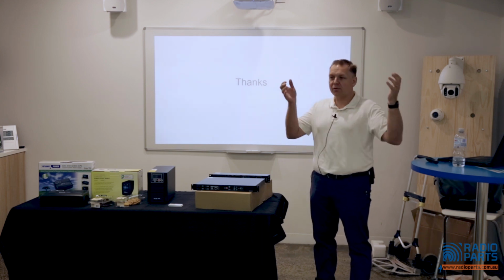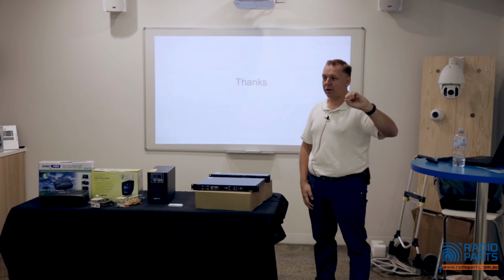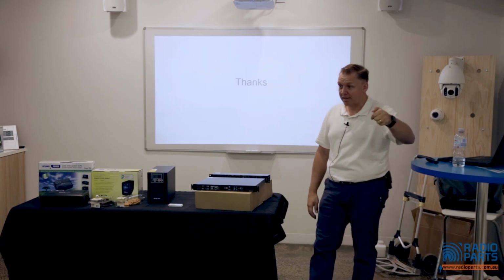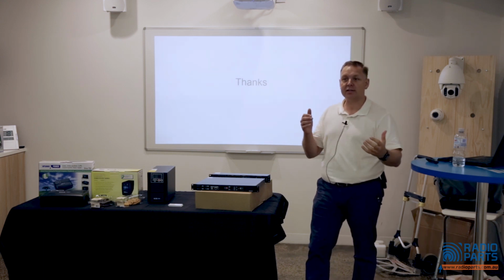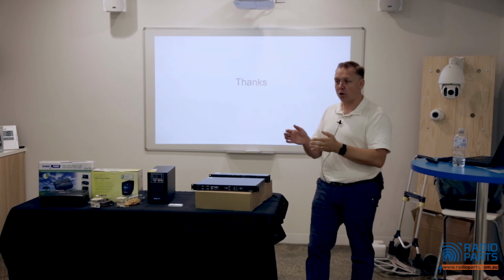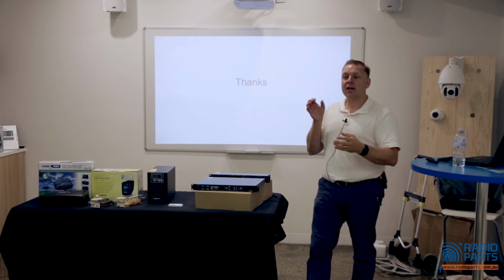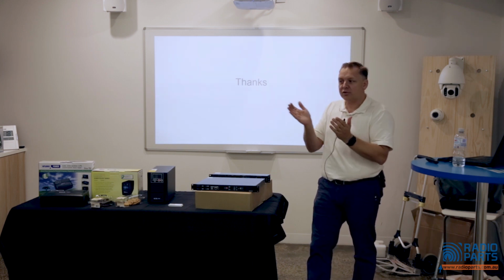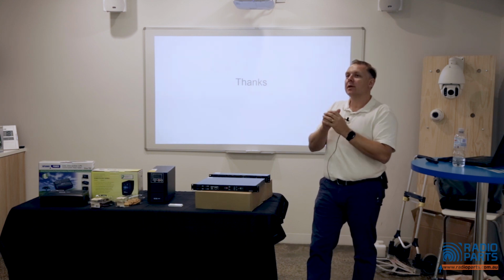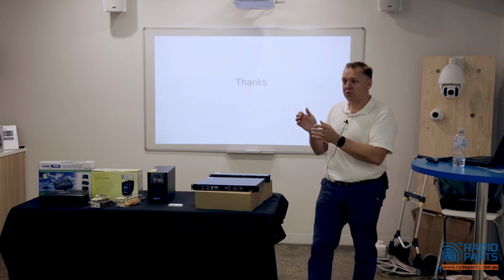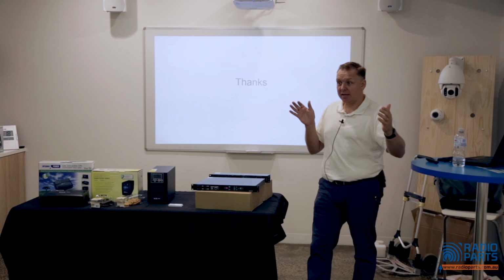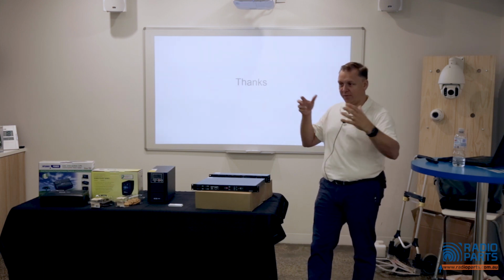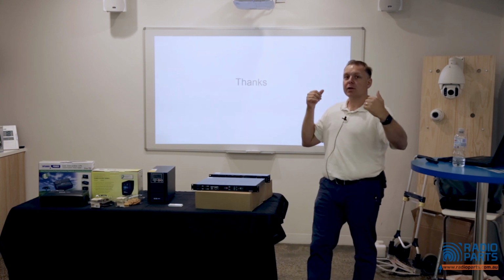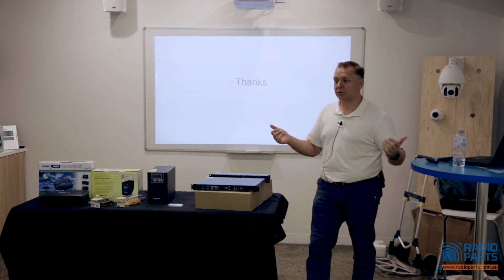They have a little capacitor in them to try and balance out their power factor. When they turn on, there's a big inrush. We know how to handle that, so you'd have fluoro start switch mechanisms to handle that inrush. All of those things, that power factor was a known thing. It didn't matter — they were all typically about 0.8, 0.9 if it had a good capacitor in it, but it was consistent. It didn't matter what manufacturer you got your light fitting from. The quality came in the fittings and all of that sort of stuff.